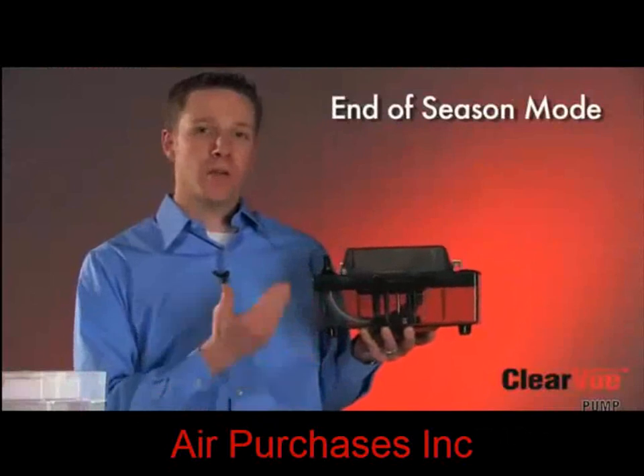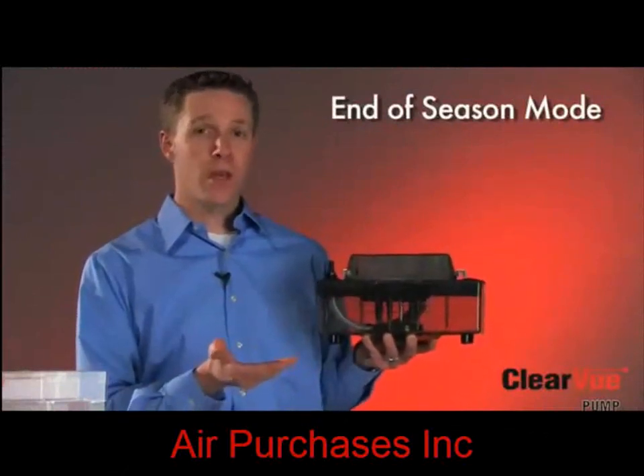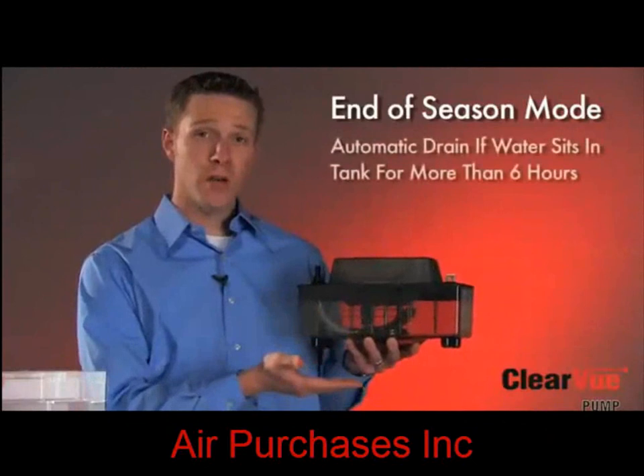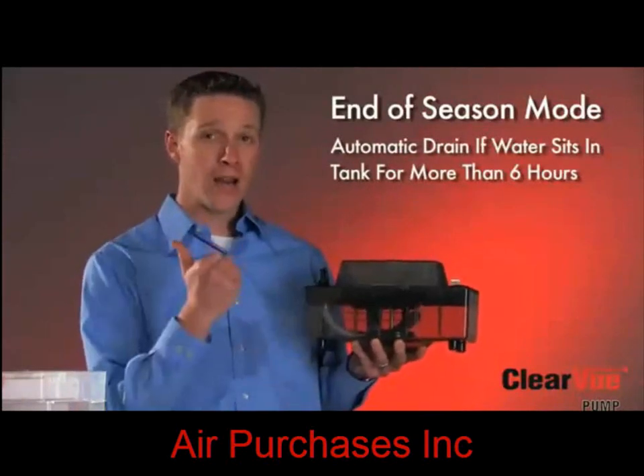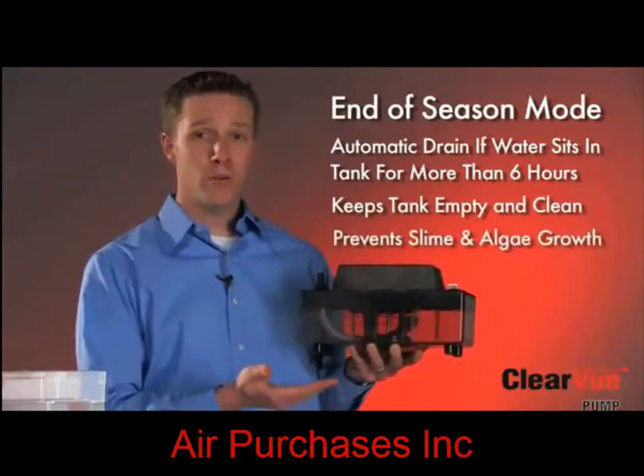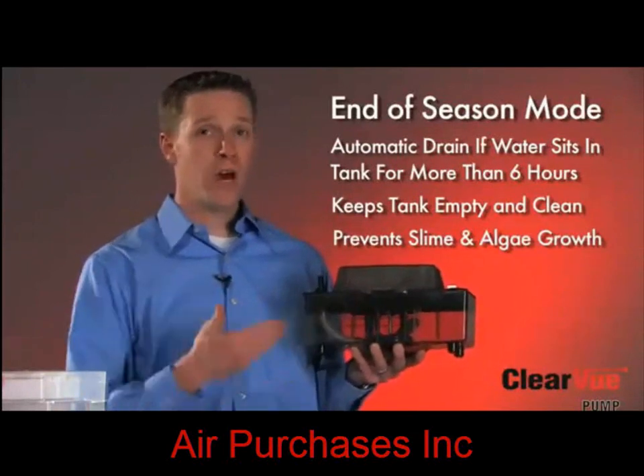The last feature I'd like to talk about with ClearVue is what we call our end-of-season mode, another part of our IQ technology. Basically, if water has remained in the tank for a period of six hours or more while touching the bottom sensor, ClearVue knows to run a pump-down cycle to get that water out of the tank to prevent any slime or algae buildup inside the tank. With ClearVue, it's almost 100% dry all the time, especially between seasons or periods of not cooling.